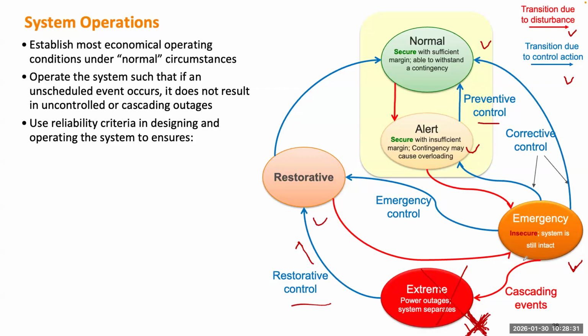Okay, then you need to design your reliability criteria or standard to make sure that if the system enters alert state, it can go back, or at least it doesn't go to emergency state. Emergency state, compared to alert state, means the system is insecure. Being insecure means some reliability standards have been violated. For instance, if you want the substation operating at 500 kV, the voltage should be above maybe 98% or 95%. But right now, after something happened, the voltage goes to 94.5%. It's slightly under the threshold, and it doesn't damage any equipment, but it violates the standard you developed.